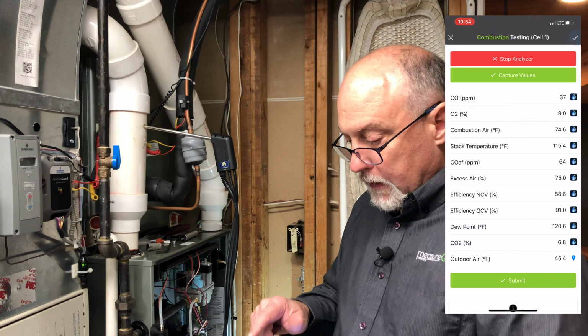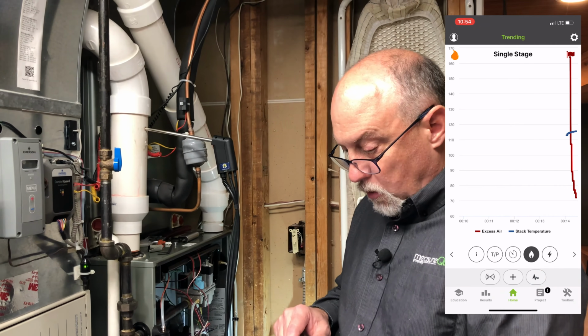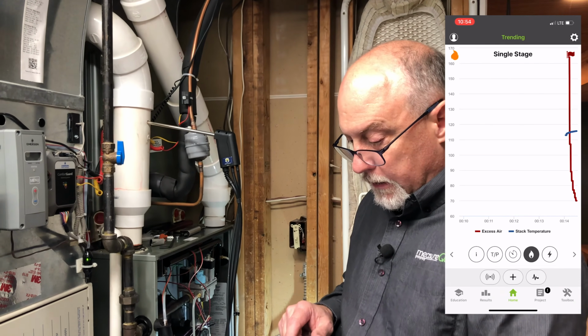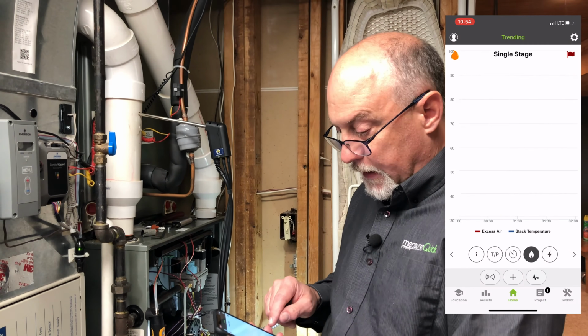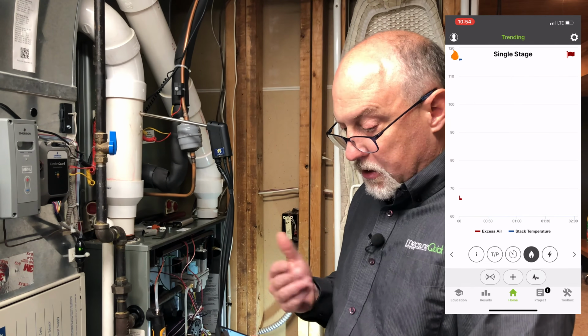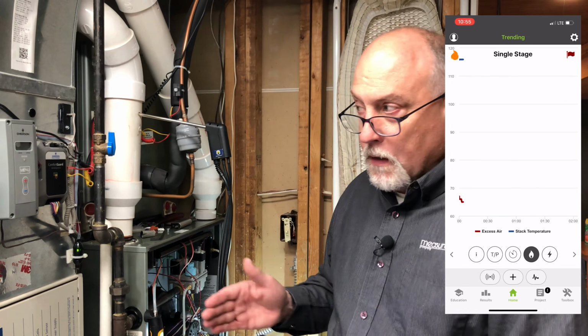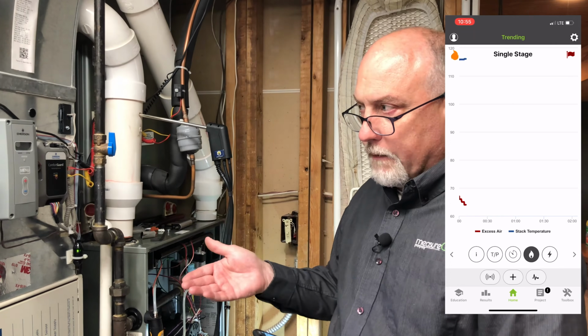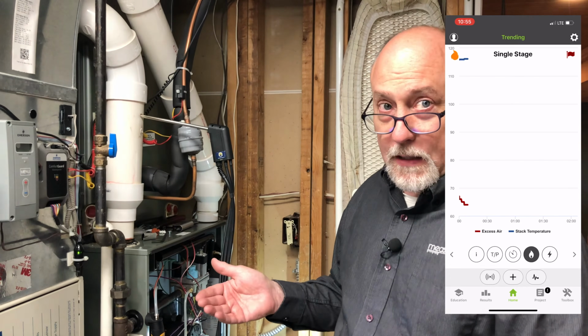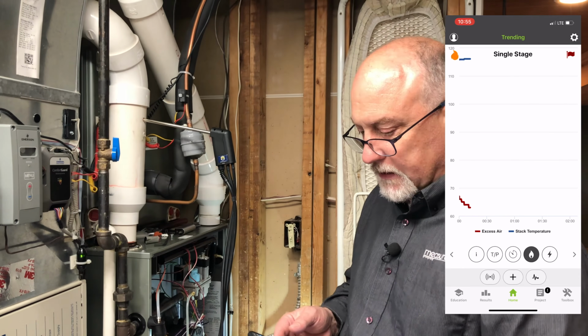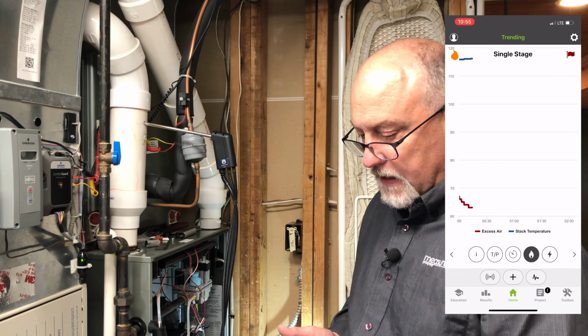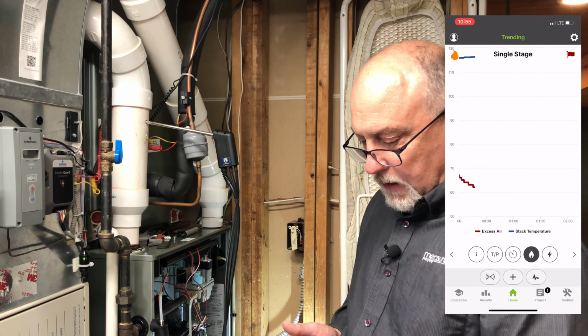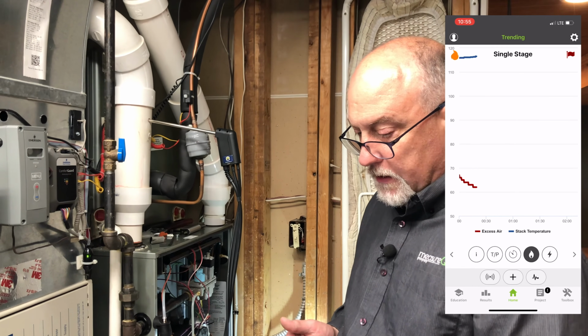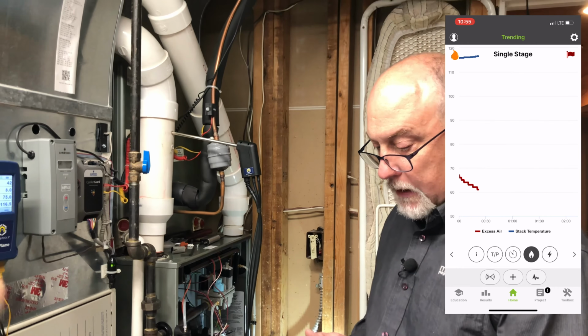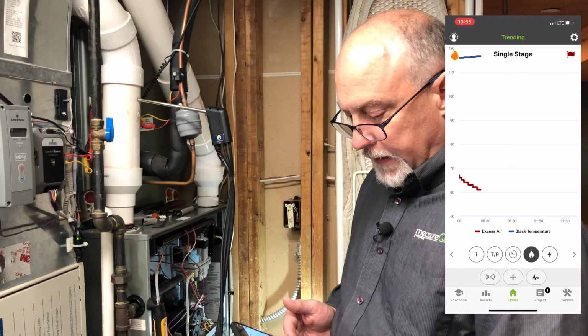Now if you want to watch it graphically, you can just scroll over here, and stack temperature is our line in blue here. I can just restart the trends because they started from the very beginning of time since we started this. And then this will just start graphing our stack temperature on the top. But because the furnace has been running, really all we're waiting for is the analyzer to stabilize. The furnace is already pretty well stabilized, and that's one of the nice things about using measureQuick to do this testing. So you can see our excess air is still dropping on this. Our combustion is still rising, so we're going to give this just a couple of minutes before we pull in our readings on the appliance.